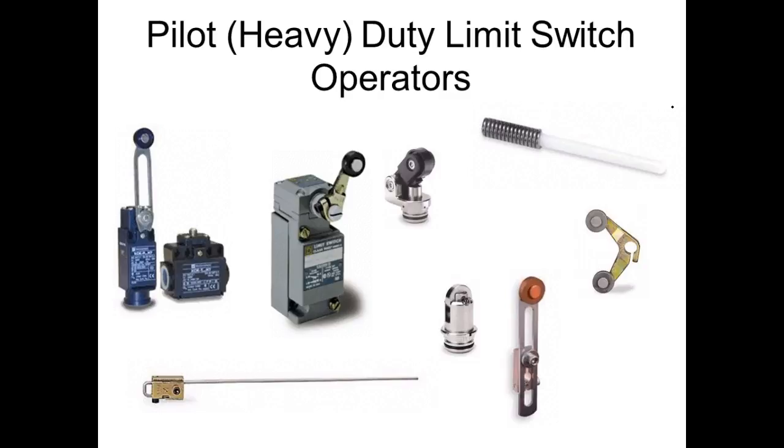Notice they have a snapping action, a hysteresis or an activation curve. So as soon as you move, they don't activate instantly. And once you hit that point, it's not a slow switch. It moves across a plateau and snaps, because the longer we take to make the contact, the more likelihood we're going to get arcs. And if we get arcs, it's going to pit our limit switch, right? You understand? And it could cause the contacts to weld together.